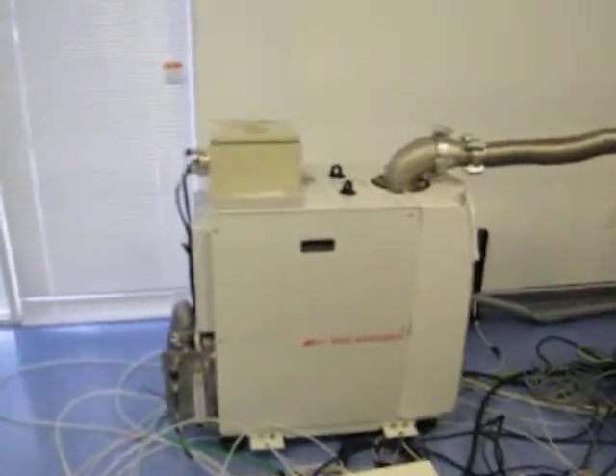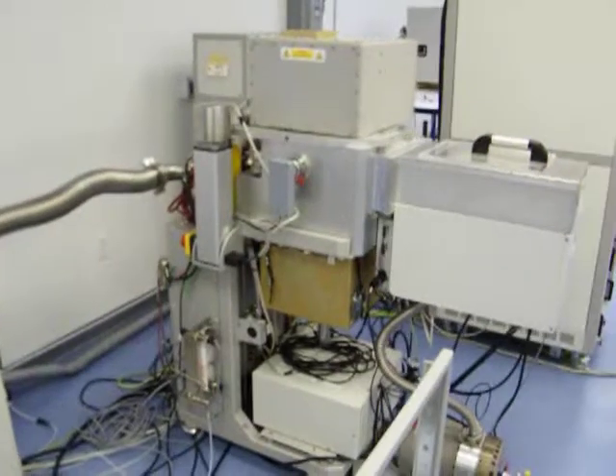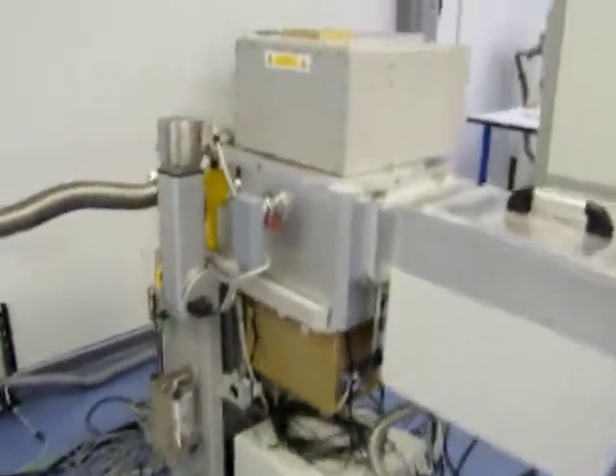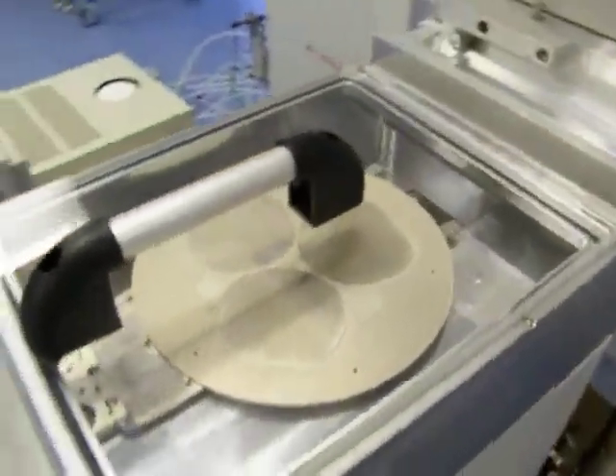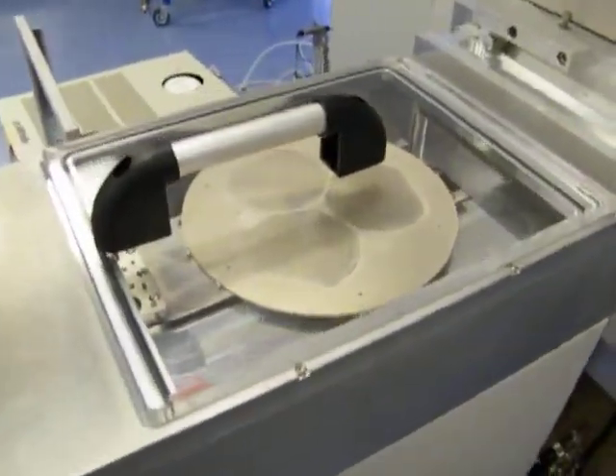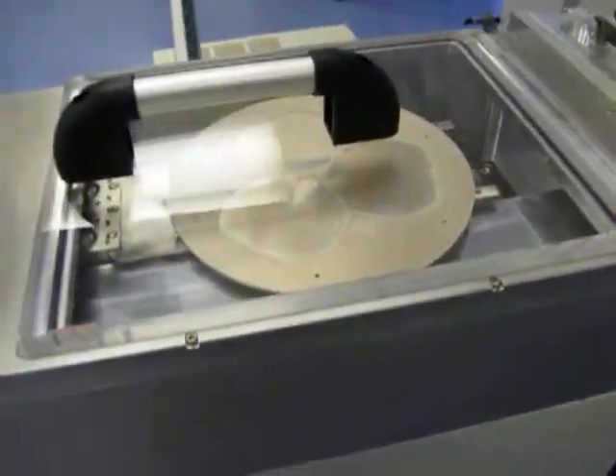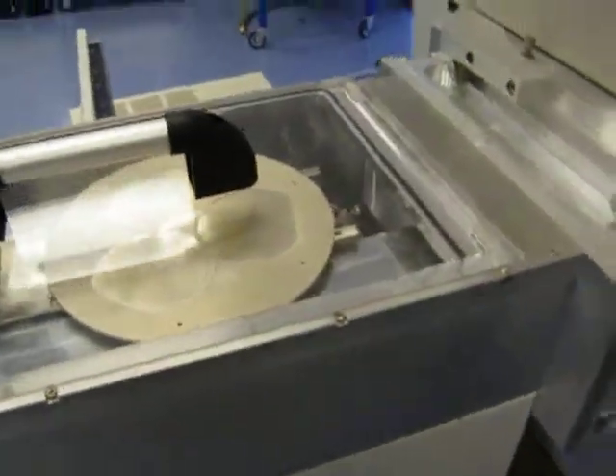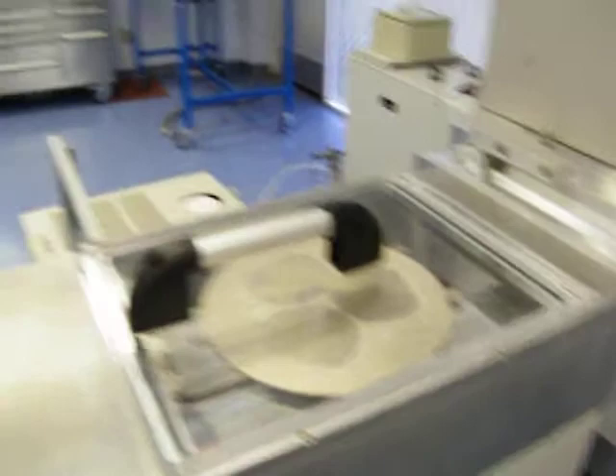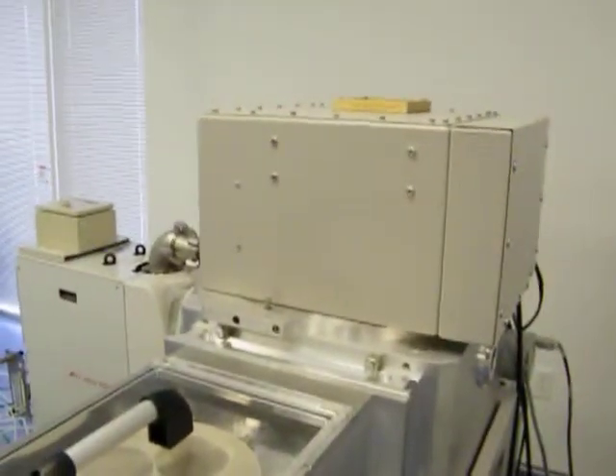The vacuum pump has been sent out and professionally rebuilt. Looking at the main system, it has a mini load lock. The load plate was made specifically for this customer — it's set up for 3-inch wafers. Brian, do you want to go over some of the details of our refurbishment process?